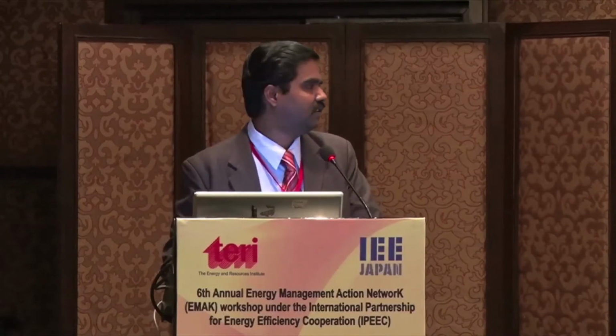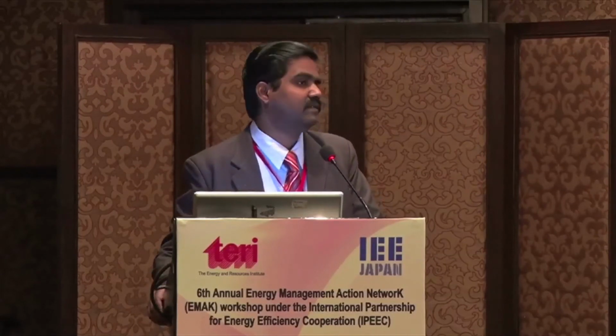This is one of the plants in Vietnam. It has been in operation for the last 12 years. It's a relatively smaller capacity of 3 megawatt. And this is the plant which I was mentioning. This is the first WHR installed in India. Not only by Kawasaki, but overall in the industry, this is the first WHR plant in India. The power output design value is 7.7 megawatt, and it has been operational for the last 11 years, from 2004. And this is the statistics for it. If you see the design value and the actual generation, the availability is around 98% versus the 94% design availability. It's almost 98% and 99%, except 1 year when it's 96 in the middle. And the design value is 7.7, but the actual generation is 8.7 or 8.8 megawatt, almost constant for the past 10 years.